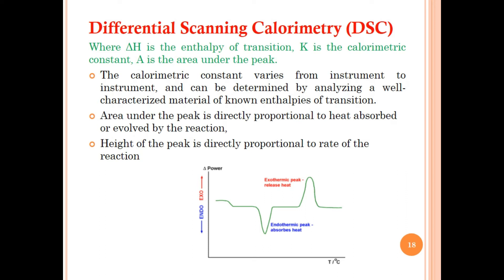The calorimetric constant varies from instrument to instrument and can be determined by analyzing a well-characterized material with a known enthalpy of transition. The area under the peak is directly proportional to the heat absorbed or evolved by the reaction, and the height of the peak is directly proportional to the rate of reaction. As discussed in DTA, the DSC curve also has maxima and minima: minima represent endothermic peaks and maxima represent exothermic peaks.